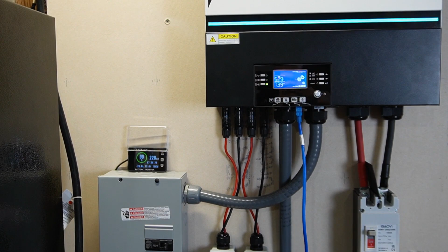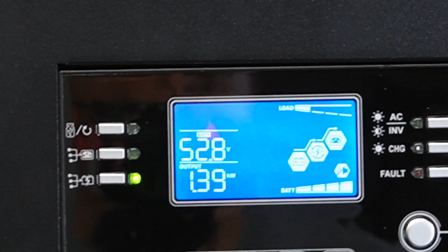Okay, so the test is off and running. I have AC turned off, I have PV input turned off. Let's see what we show here on the inverter. We're totally running off the battery right now - there's no PV input, there's no AC input. We're pulling about 1.39 kilowatts to charge the EV.